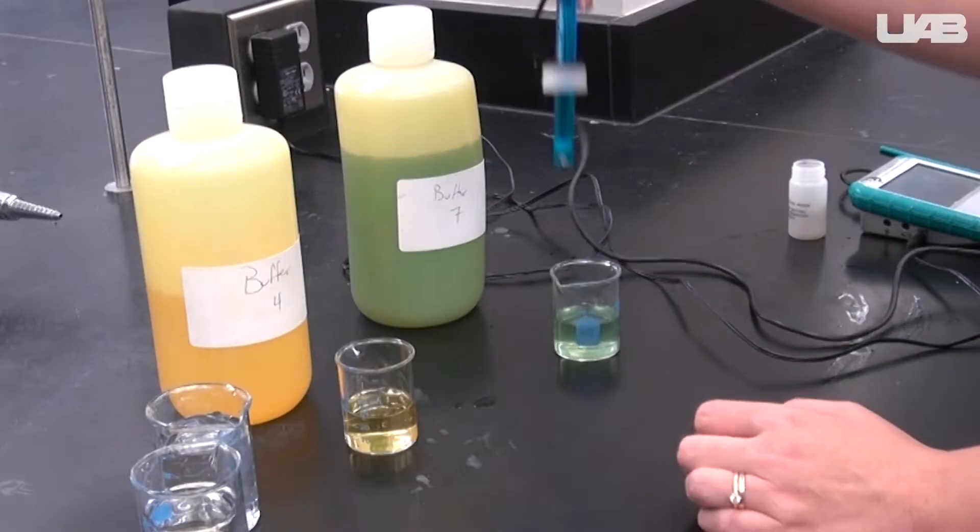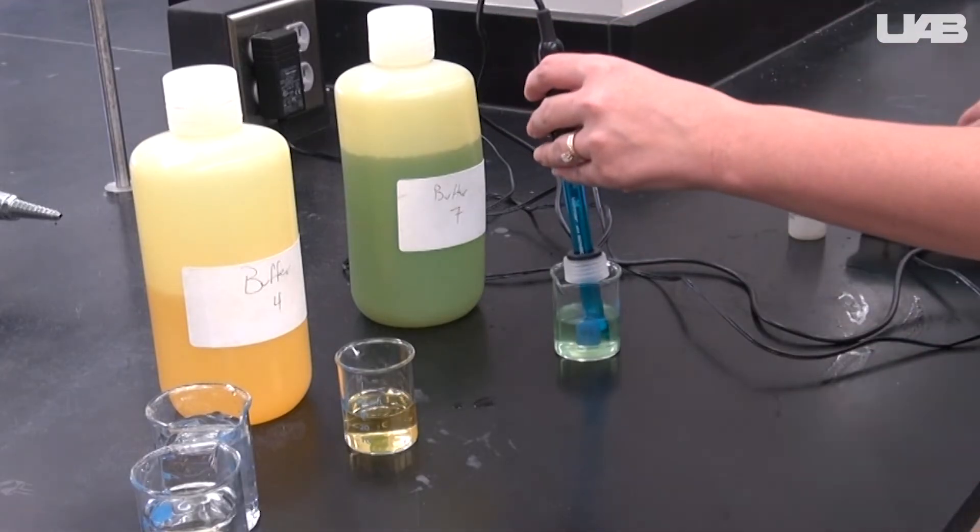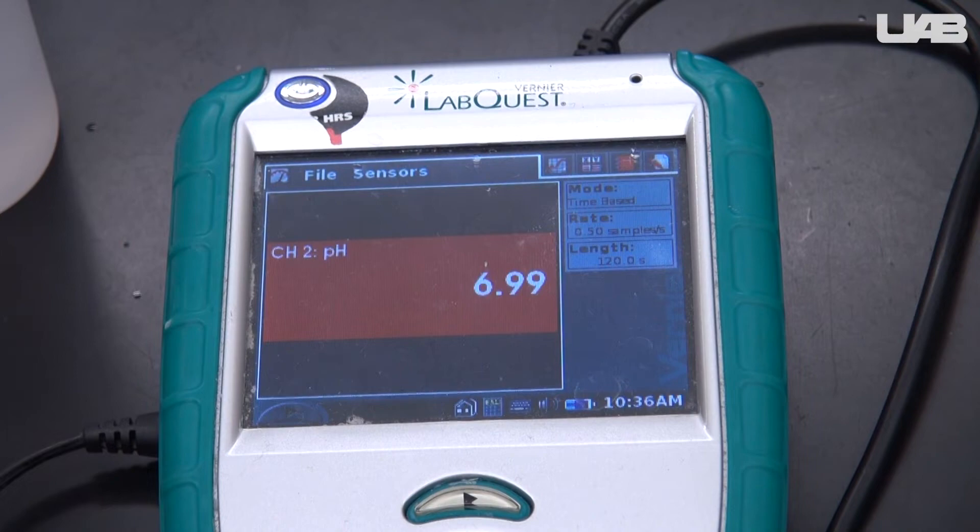Rinse your probe again and place it into the pH 7 buffer to ensure that the meter is now reading the pH correctly. You should see 7 on the screen. You are now ready to begin taking your pH measurements.